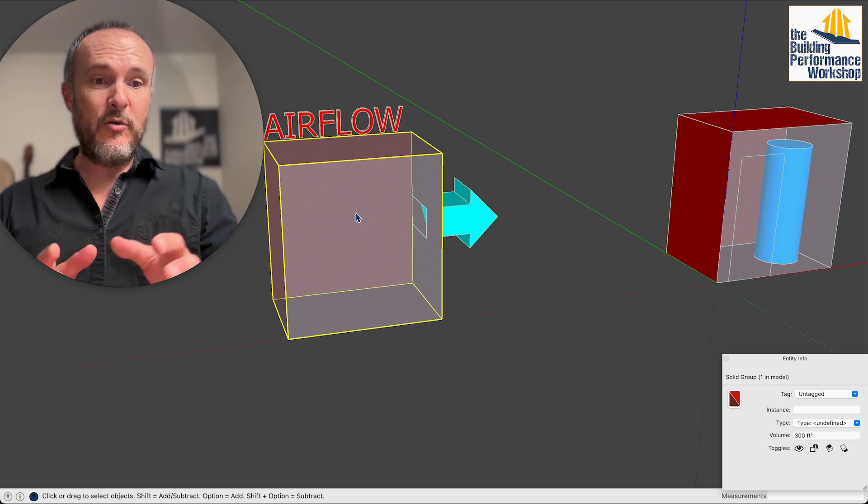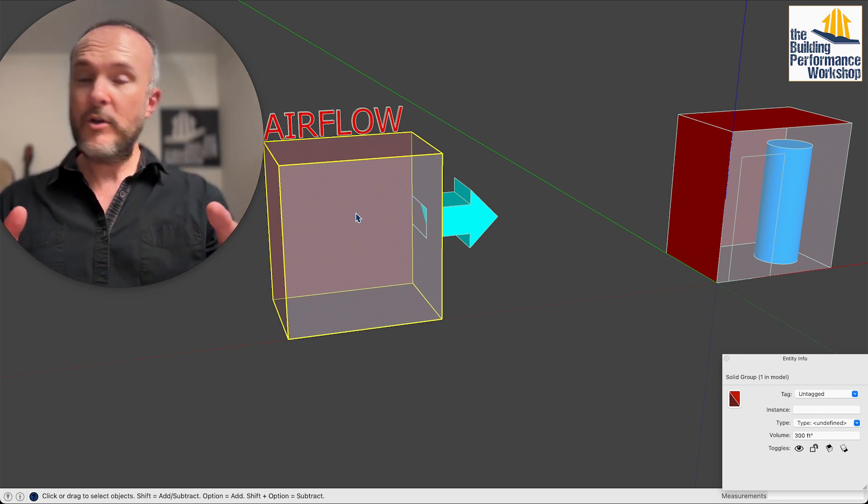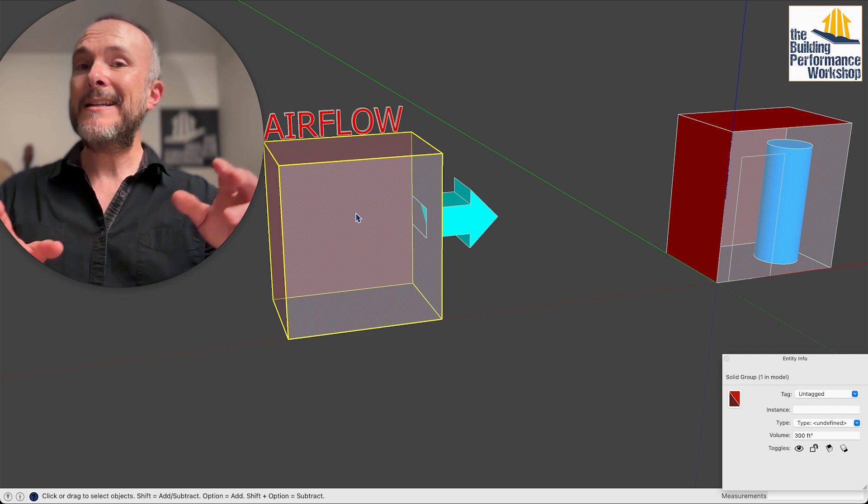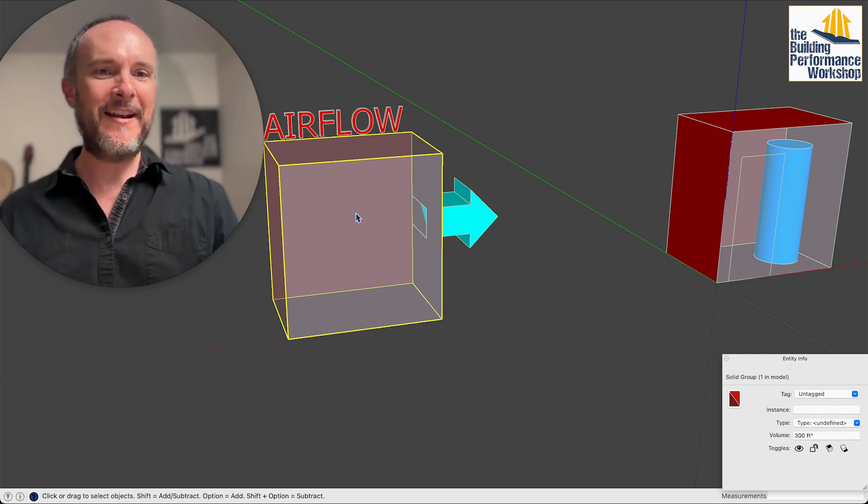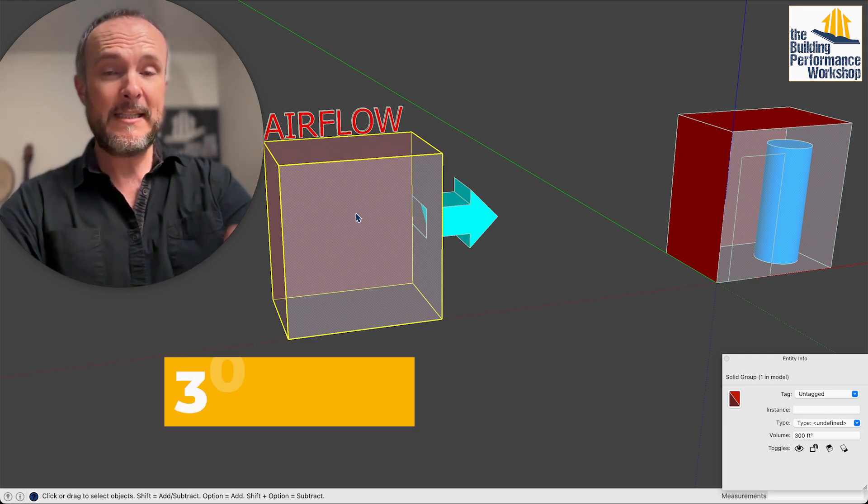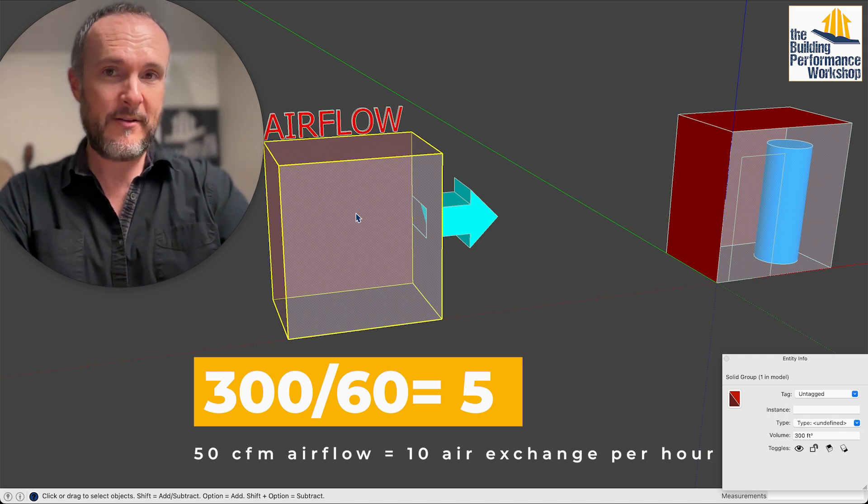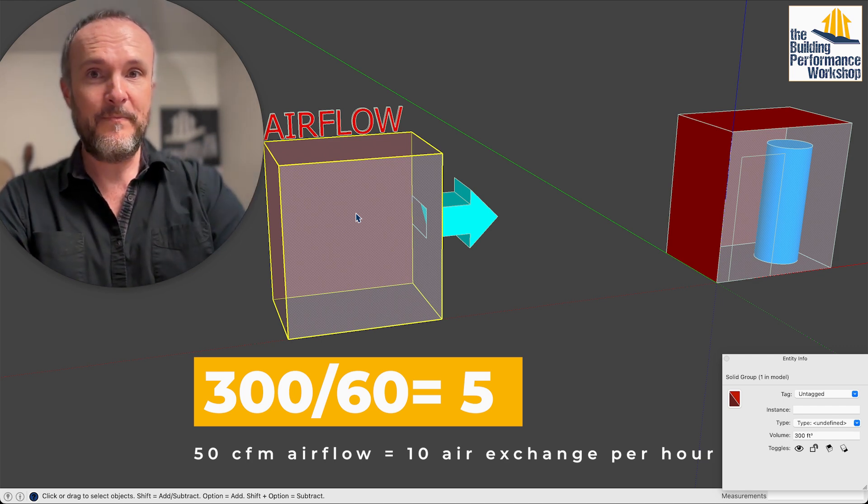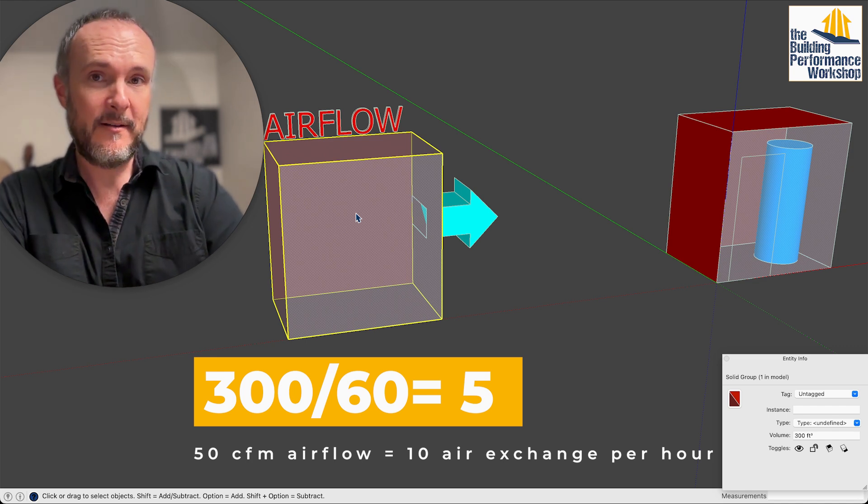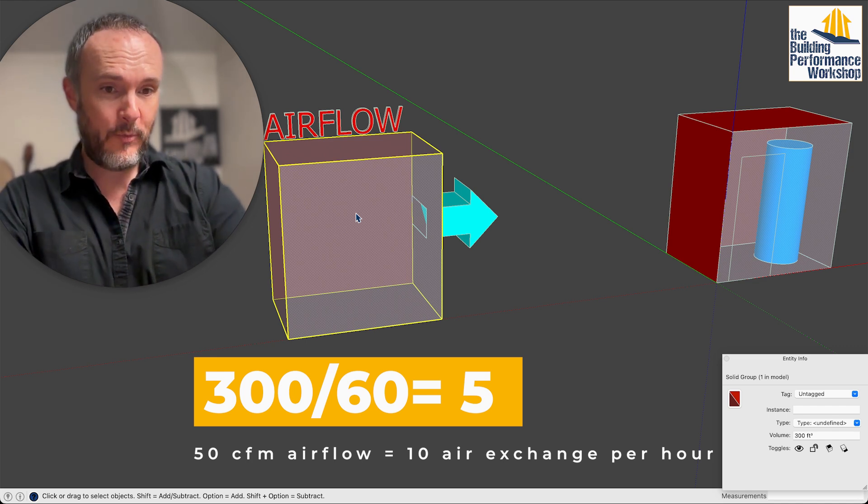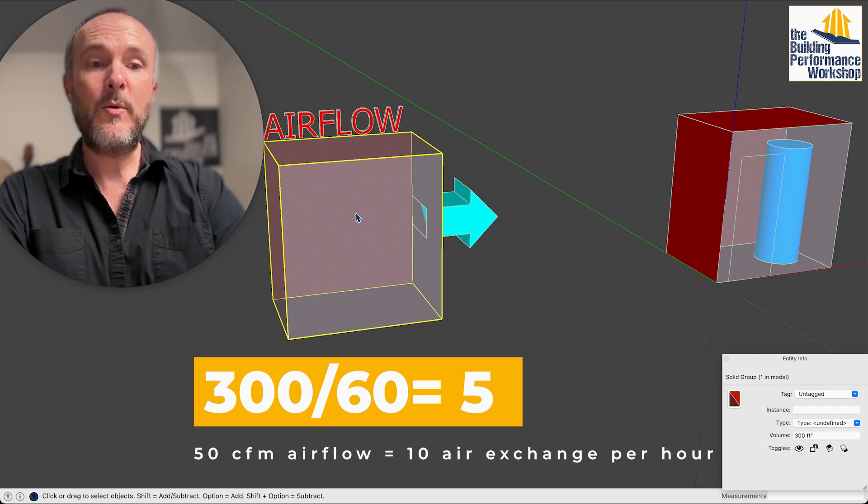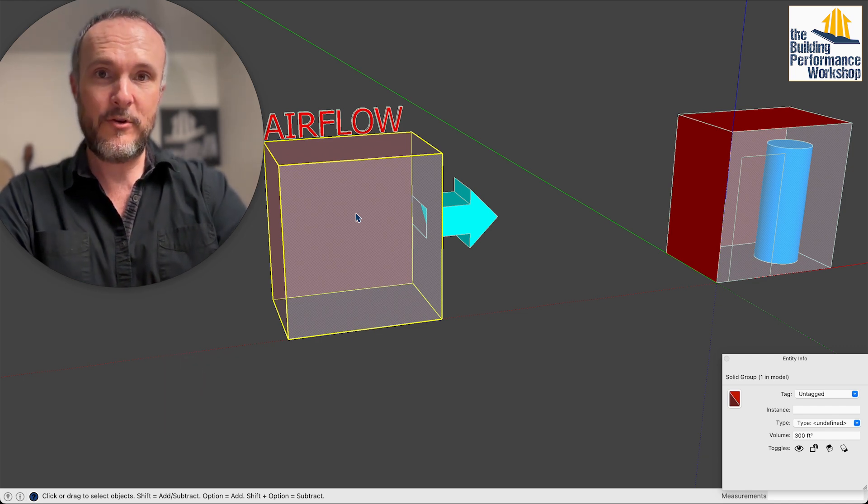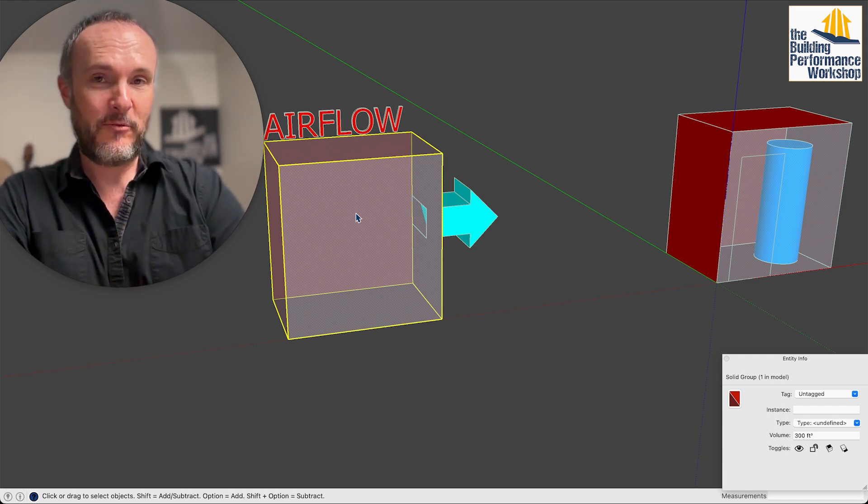That would give you a 600 cubic foot room which still isn't enough so you need to go up to like 7 CFM. Still a computer fan, but you can imagine that if you put a 50 CFM bath fan in there and run it 24 hours a day, you could change out the air inside that room 10 times an hour and that would mean that you turn a 300 cubic foot room into a 3,000 cubic foot room, four times the size that they're requiring.